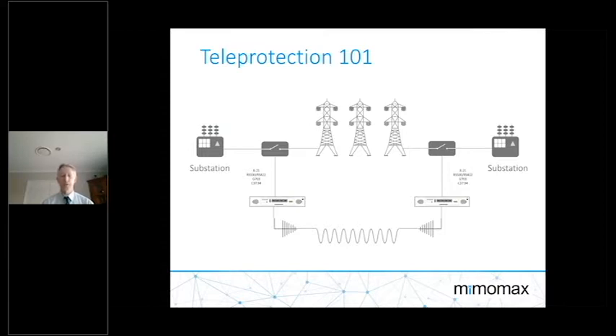Often there are requirements around how quickly we want to switch these relays, and that's often fractions of a cycle - if we're talking 60 hertz, that's around 16 milliseconds. While standards would often say you can operate within 3 to 5 cycles, the sooner we can get those relays tripped the better, and that's often dependent on the communications link, amongst other things that might sit in the chain.